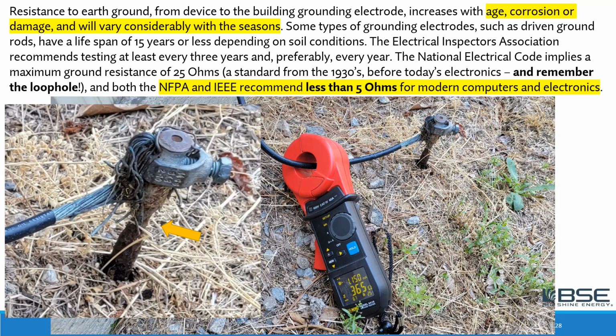So even if our building had a great grounding system when it was new, it may become not so good, and may become totally inadequate due to all of these factors: age, corrosion, and soil conditions. So here, this happened to be a commercial building, which is a little surprising. And they actually had a driven rod grounding conductor outside the building, but it was exposed, which makes it very vulnerable. And you can see it's completely corroded.